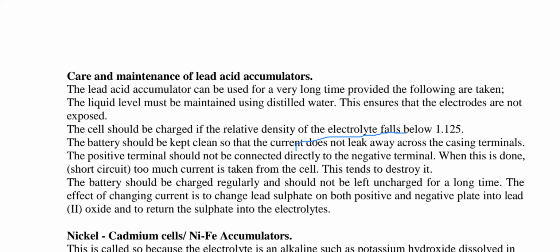Why do we maintain the liquid level? The work of that distilled water, what we pour there, is to ensure that the electrodes are not exposed. That's the first thing you need to know if you want it to work very well for a long period of time.